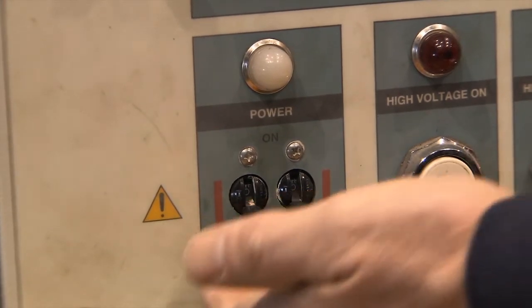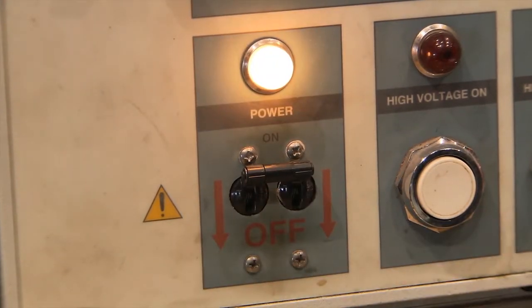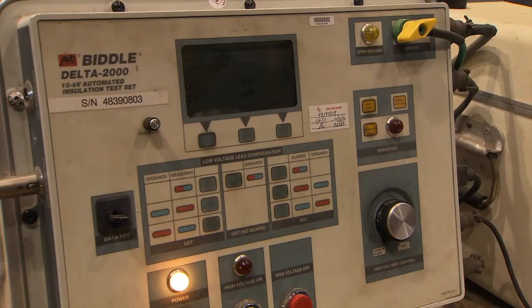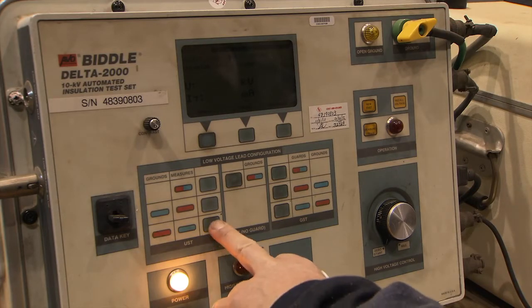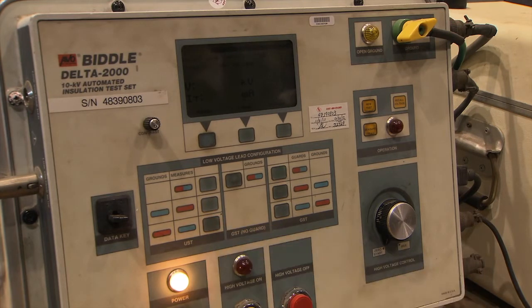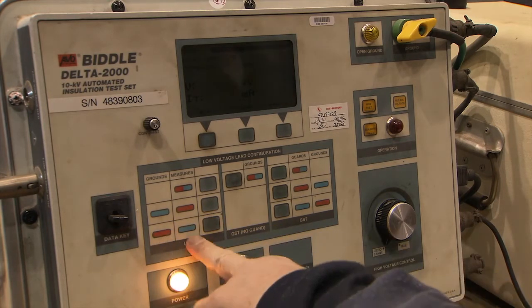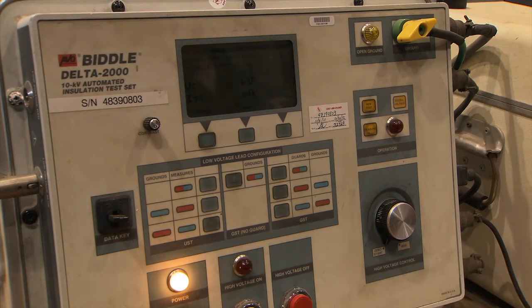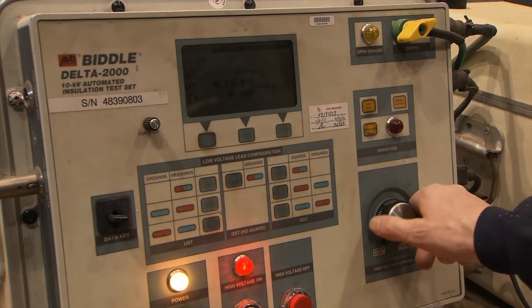Turn power on switch on Biddle. Turn on the high voltage switch. Press the UST test mode button for grounds red and measures blue option on the low voltage lead configuration panel. Press the high voltage on switch and the red light goes on above.